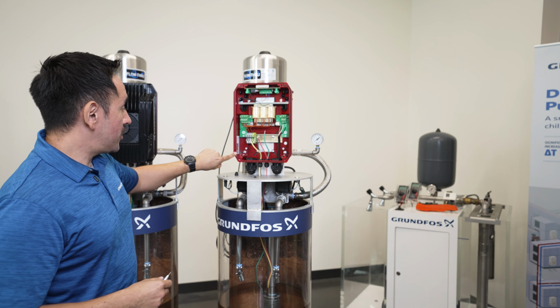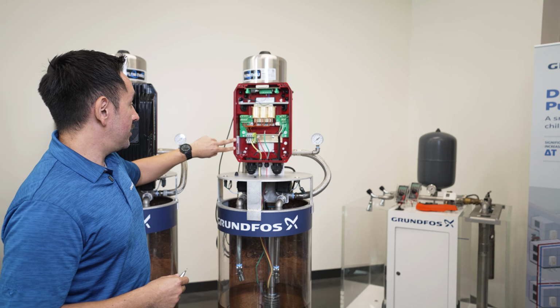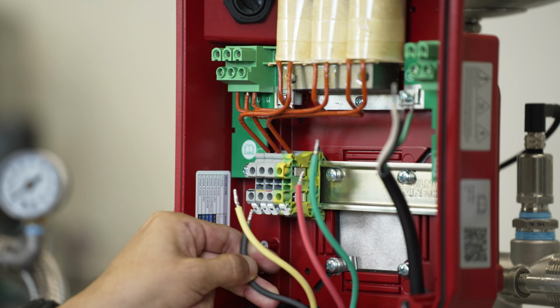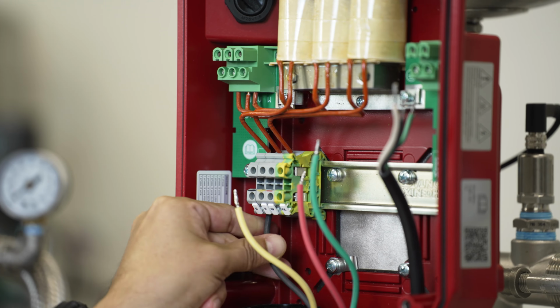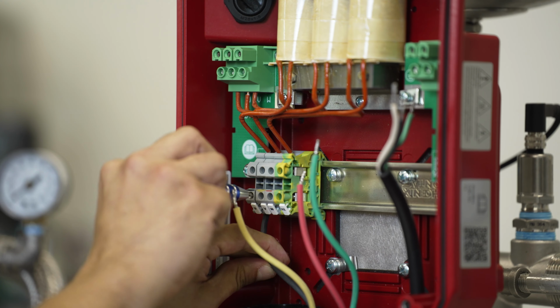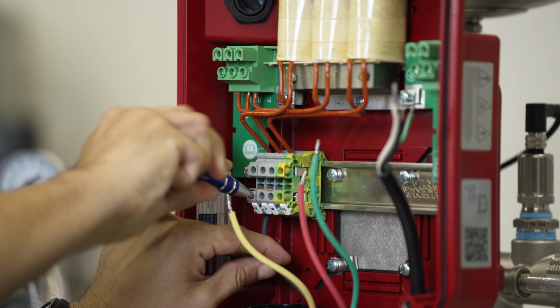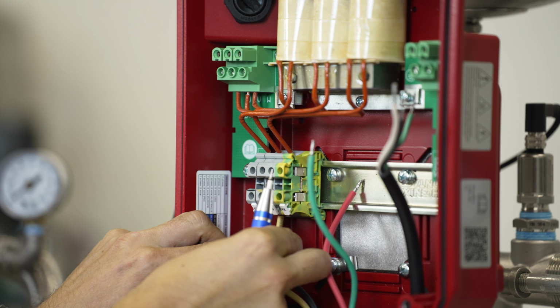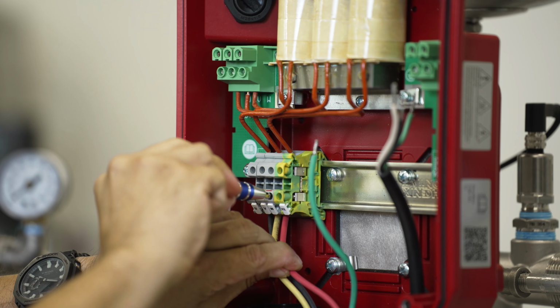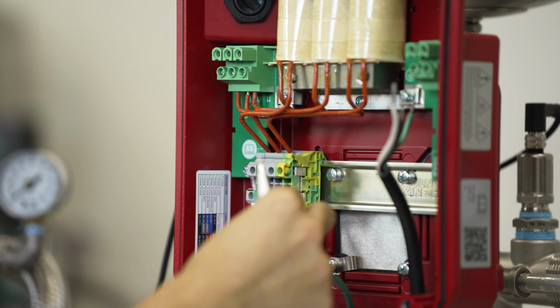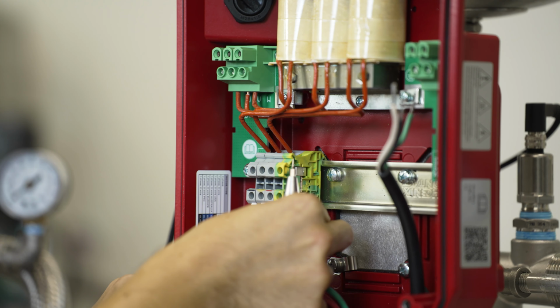While looking at the color-coded sticker that we have inside the casing, this motor is a single-phase, 3-wire motor. So you will have a black, a yellow, and a red wire. The black will go into terminal U, yellow will go into terminal V, and then red will go into terminal W. And then, of course, the ground into the earth or PE terminal.